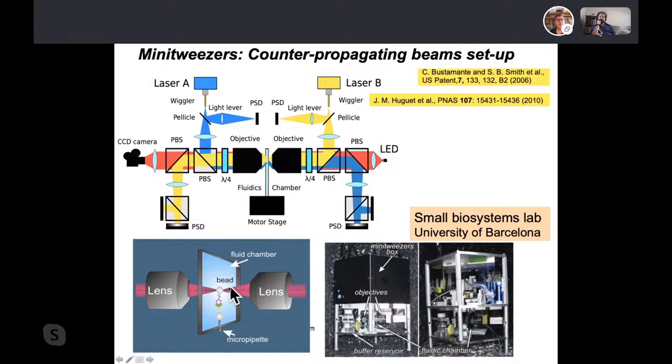If you impose a deflection by this refraction behavior, then there is a change in linear momentum of the light beam. The speed of light doesn't change, but you change the direction of the beam, so there is a change in light momentum. Now it turns out that these detectors can measure exactly this change in light momentum, from electromagnetic theory, by measuring the Poynting vector.